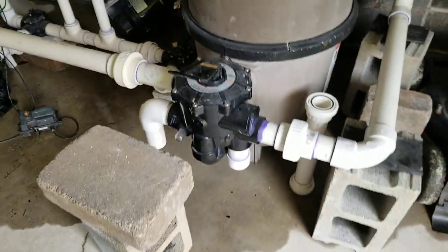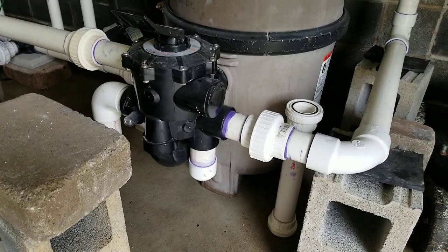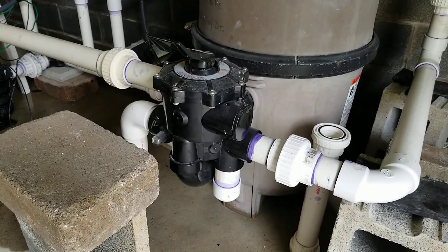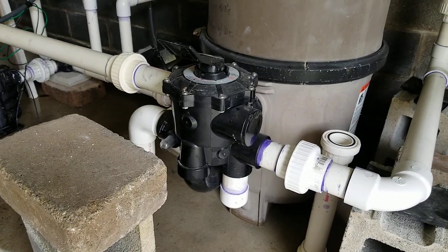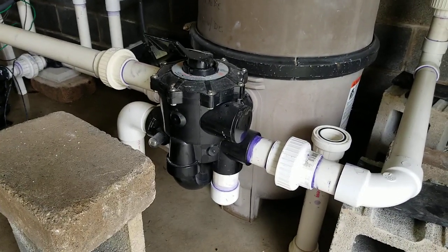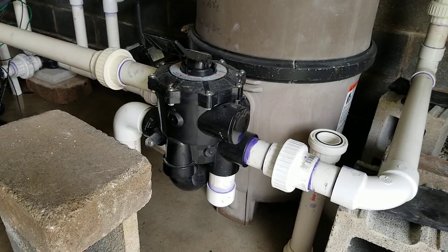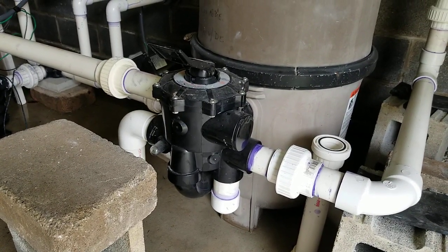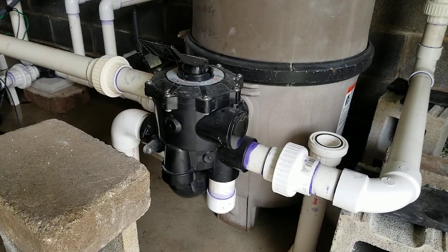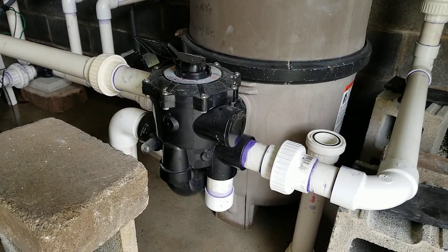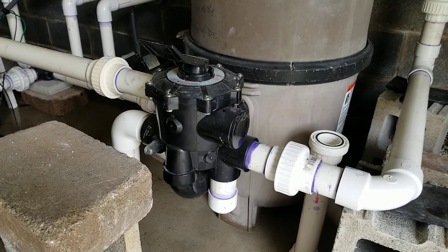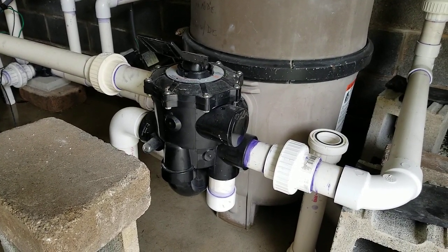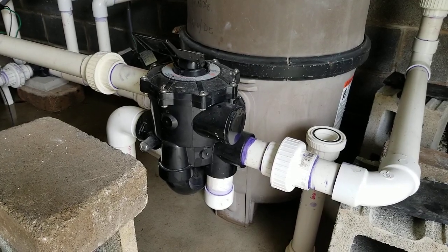What the internals of this diverter valve look like, I don't know, but there's some kind of tortuous path that the water has to flow through. So we're going to treat this as some kind of weird fitting. We do not know what the equivalent L over D is for this device, but we're going to calculate it. I'll come back to that in a couple of minutes. So this is an unknown as far as taking inventory of all the losses in your piping system.